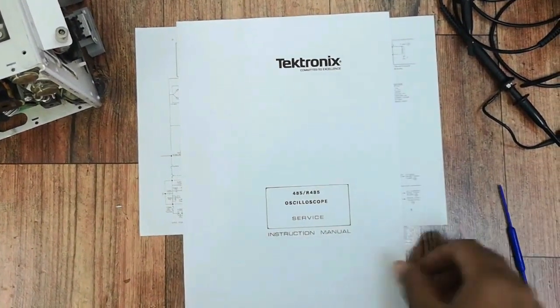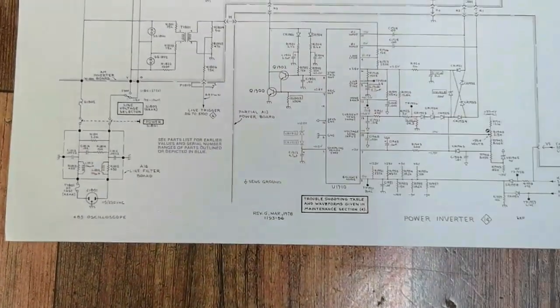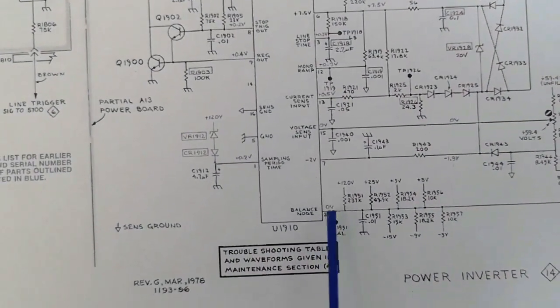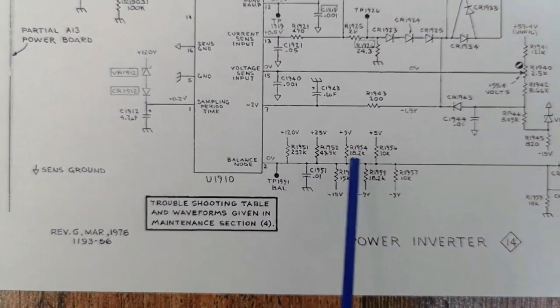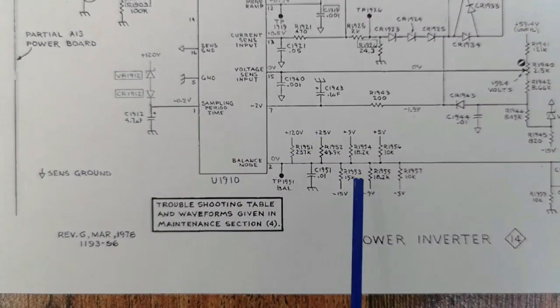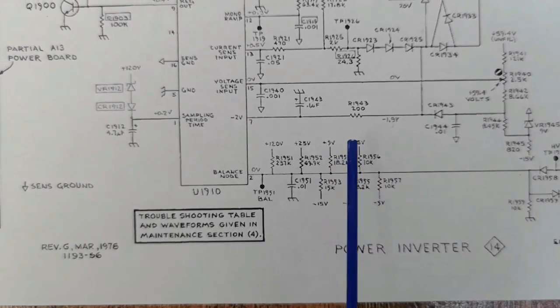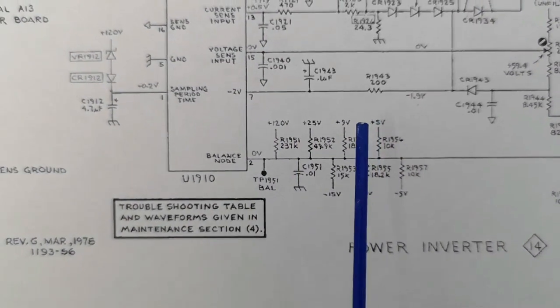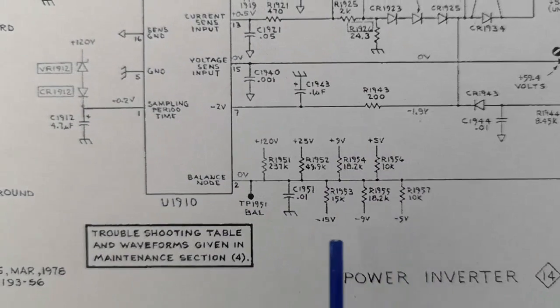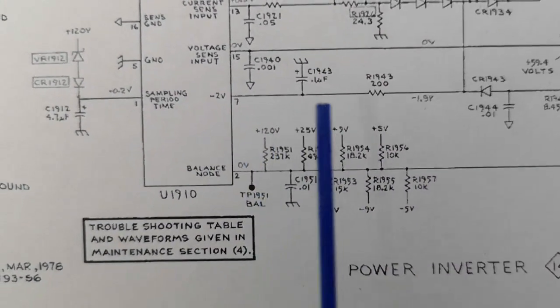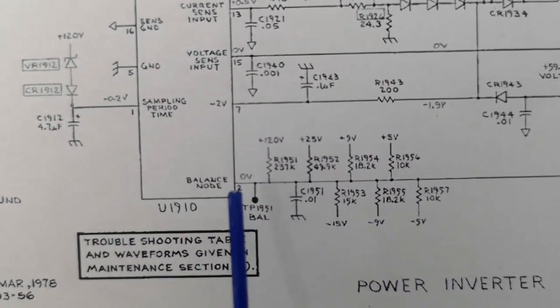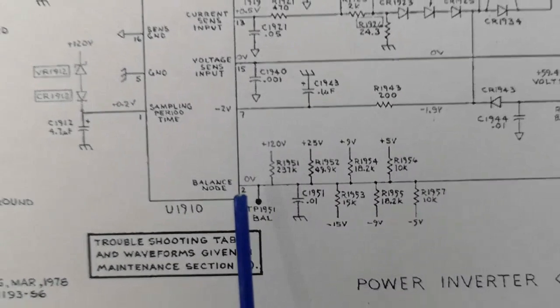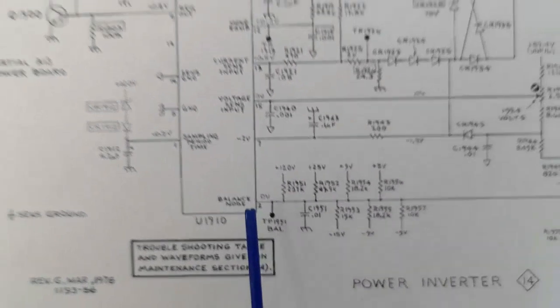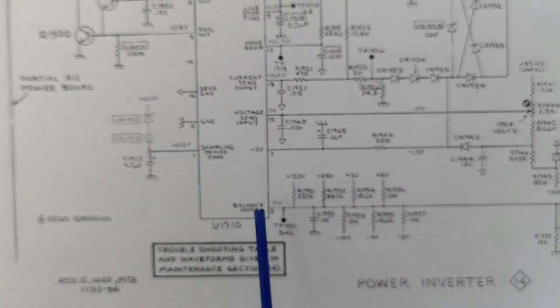And as per the manual troubleshooting steps, this can be caused by a number of reasons that will shut down the power supply. Balance node input can be one of the causes. This input, through a set of resistors in the circuit, keeps monitoring a voltage balance of some positive voltages against other negative voltages. If any of these voltages goes out of range, the input voltage at pin 2 will either rise above 200 millivolt or drop under minus 200 millivolt, depending if the fault is at the positive voltage side or the negative voltage side, and cause shutdown.